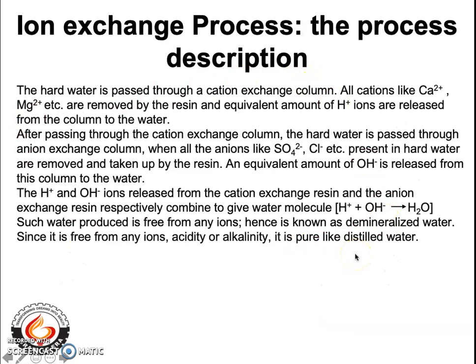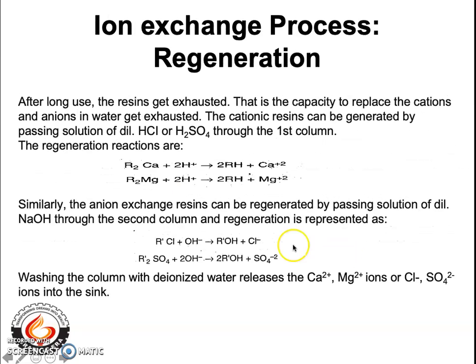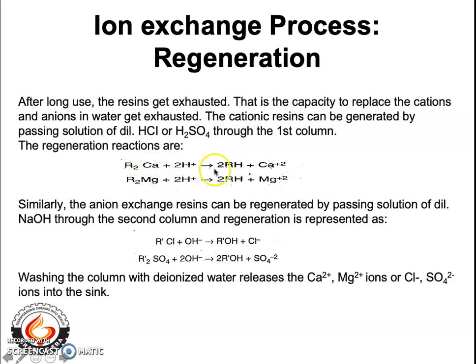Now let us come to the regeneration process. After long use, the resins get exhausted — meaning the resin loses the capacity to replace the cations and anions present in hard water. The cationic resins can be regenerated by passing a solution of dilute HCl or H₂SO₄ through the first column. The H⁺ ions present in HCl and H₂SO₄ get bound to the resins, and what comes out is calcium ions or magnesium ions. So the cationic exchange resin is now regenerated.